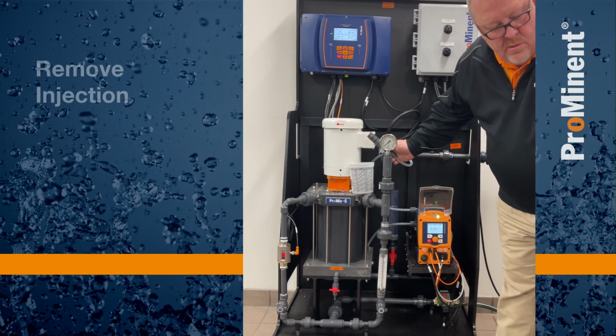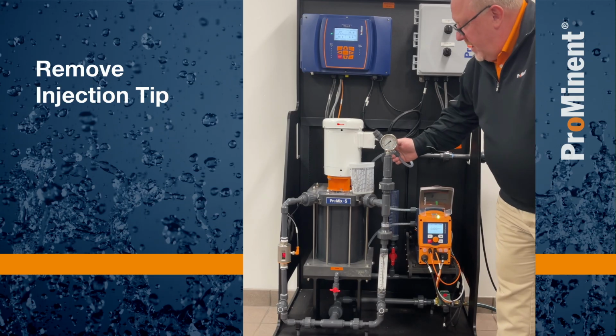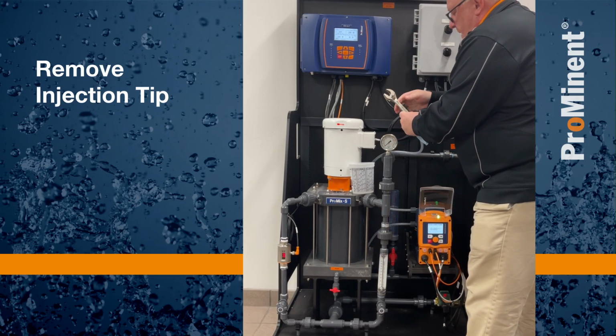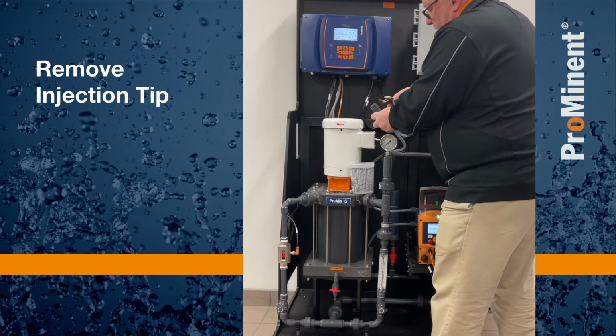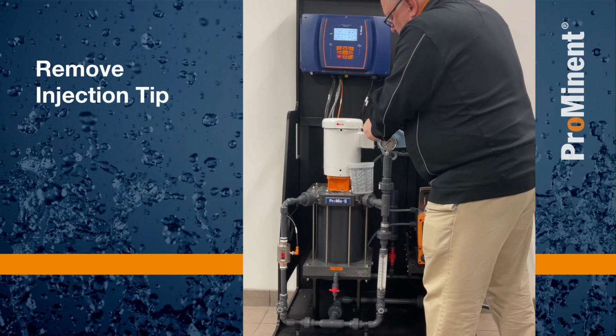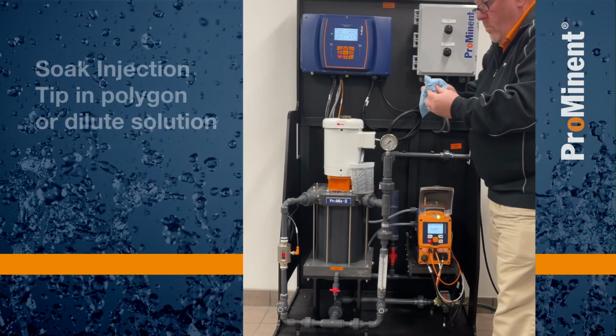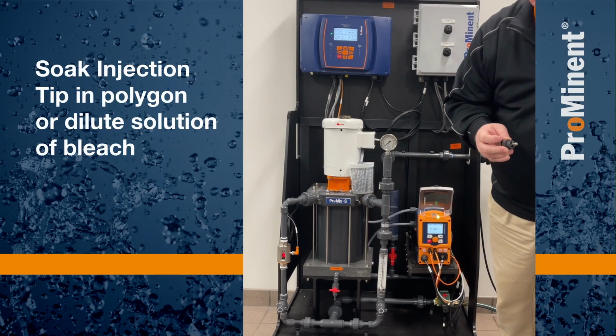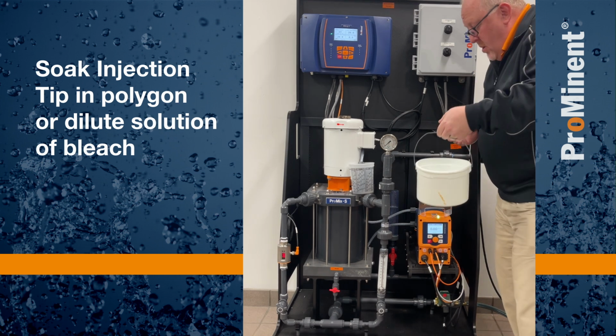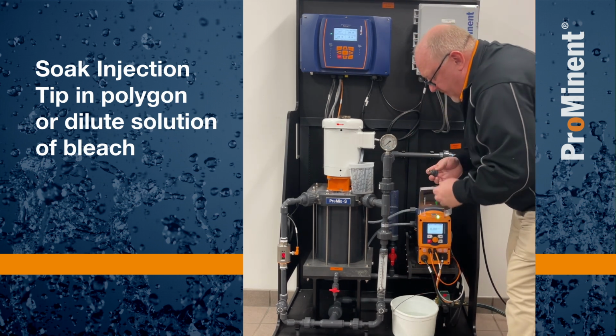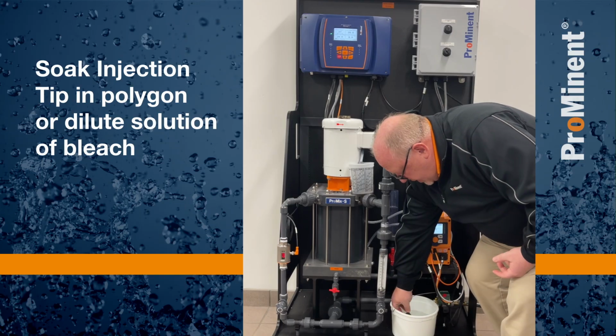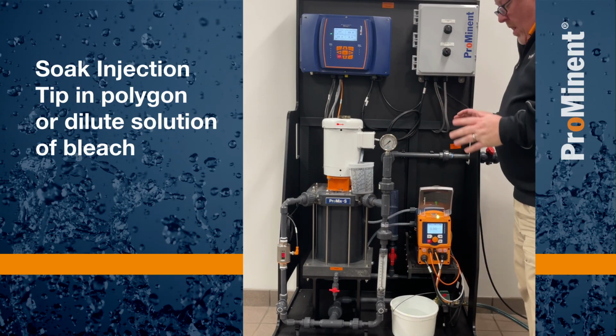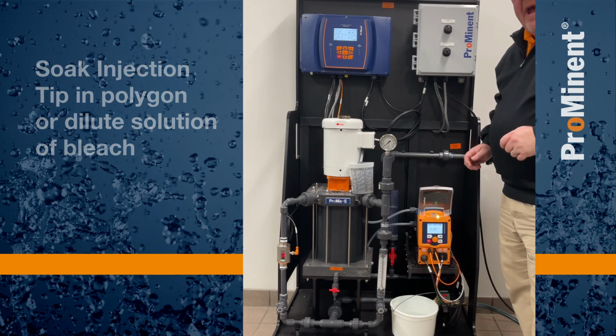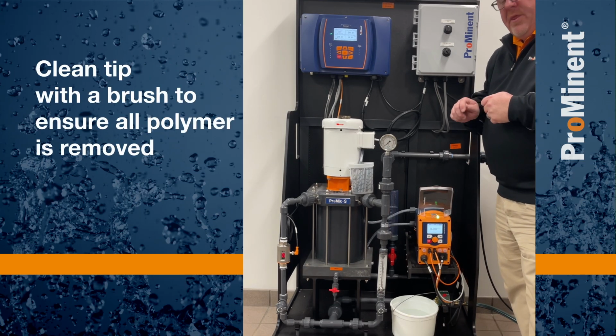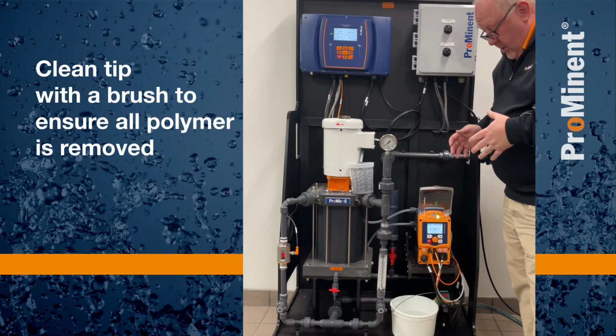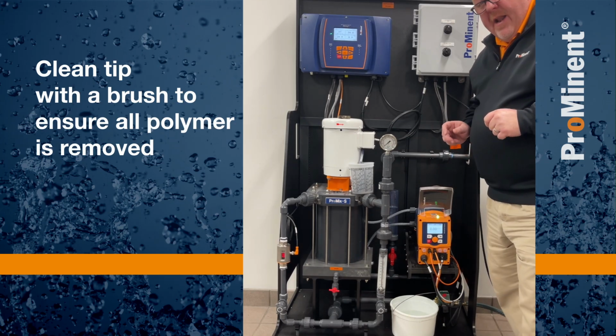Now we're going to loosen our fitting. The tip of the injection valve is slotted, so we can get our wrench on there. And the tip, which is the checking portion of it, just threads into the valve plug. Now what we can do, we can have a bucket filled with either Polygon or a dilute solution of bleach, and we can let that injection tip just set in there for a period of time while we're cleaning up the rest of the skid. We'll come back, we'll get that tip, we can clean it with a brush. Just make sure that all of the polymer is removed from the tip of that injection valve.